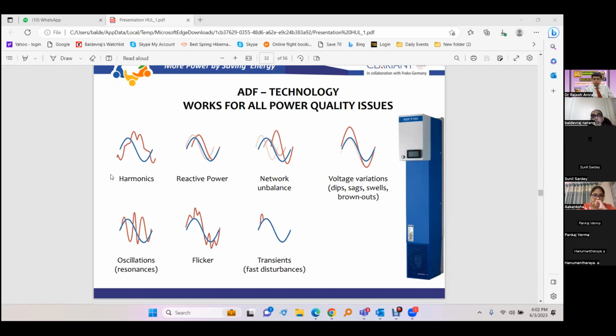In passive, what we have seen is we are giving a low impedance path for the harmonic to flow and get diverted and not go to the grid. But here what we are doing is we are killing the harmonic. We are just giving an opposite current and neutralizing that. So the working is different in that way. So it can be used for harmonic correction. We can also use it for reactive power support, as in STATCOM. We can generate 50 Hertz current, leading or lagging, and inject it into the system. So it works as a STATCOM.